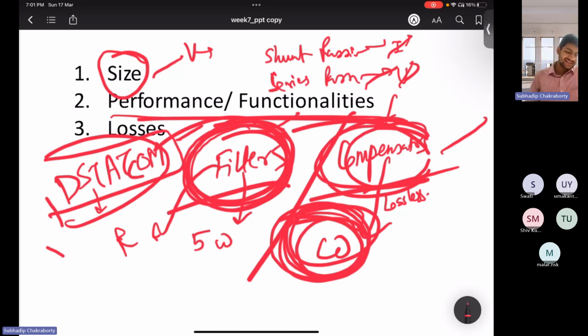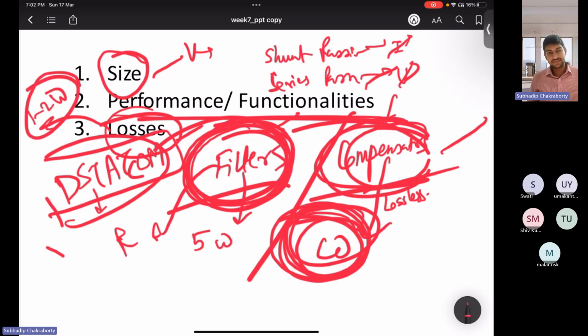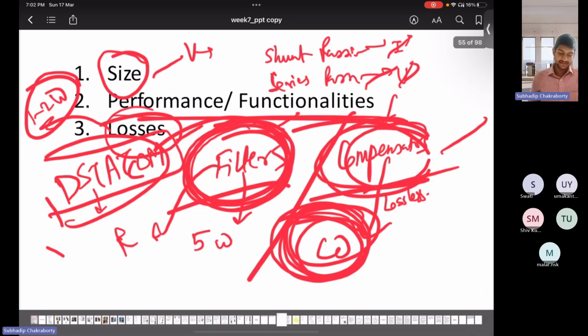And these filters have some losses, because they have resistances, as I told you, due to the damping that is necessary for filters of a particular tuned frequency to limit the current during resonance. But their losses are very less because the sizes of these filters are very small. The magnitude of R and L and C are all very small, and hence the drop is also very small, and that leads to very low loss, I can say 1 to 2 watts, for a high rating system. Like if the system is in kilowatts, you will only account for 1 to 2 watts of loss across the filters.